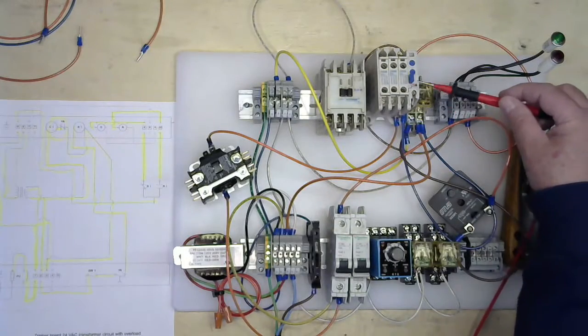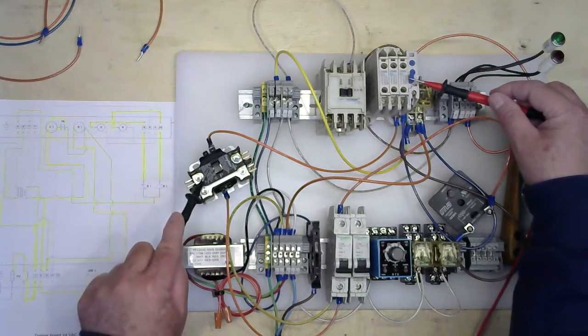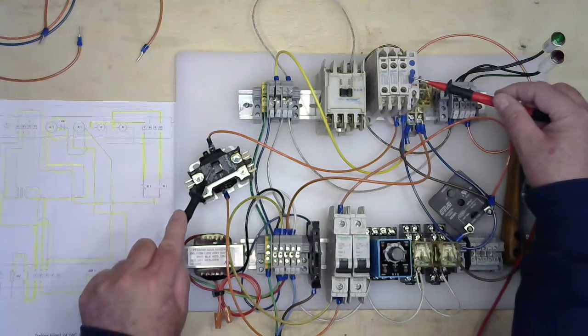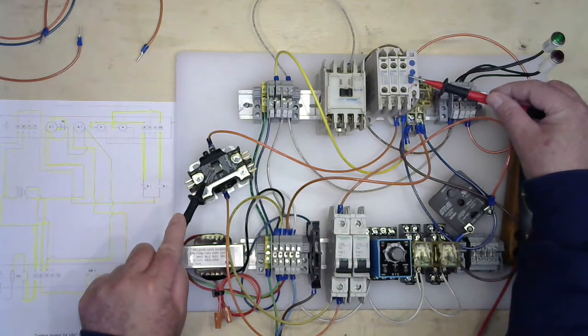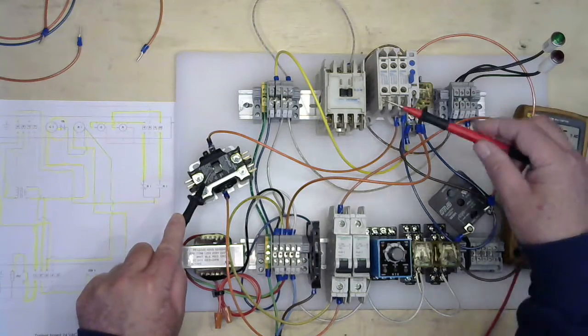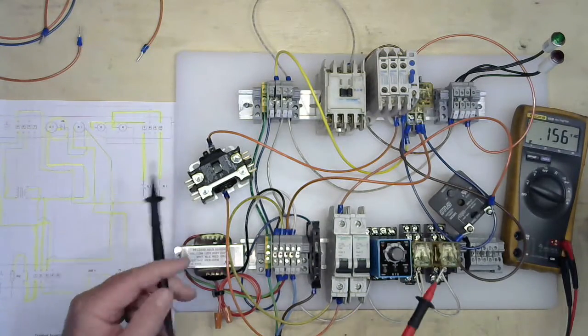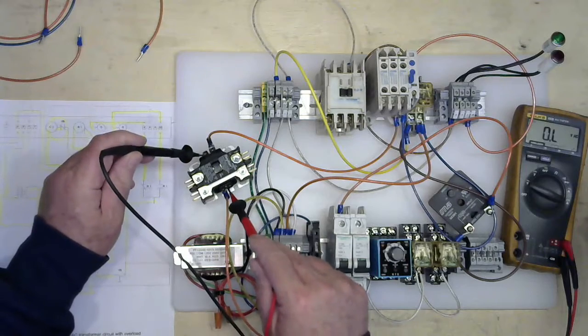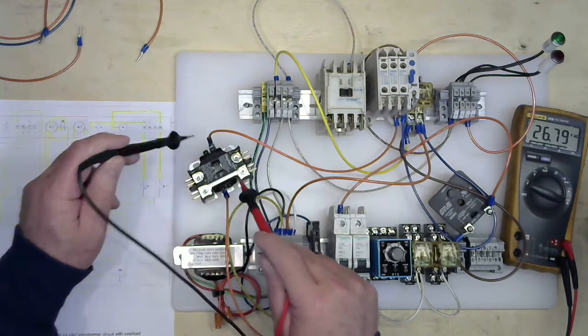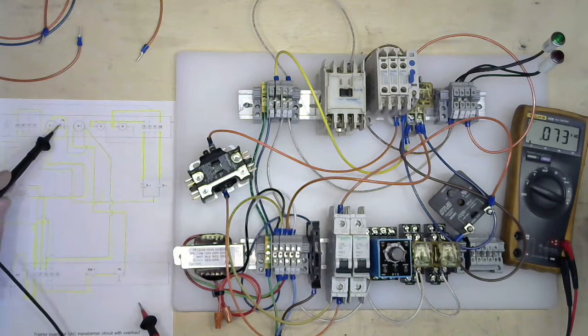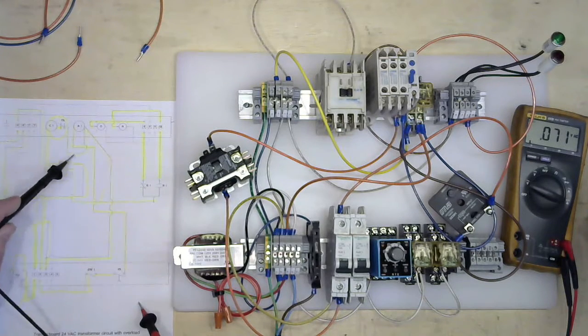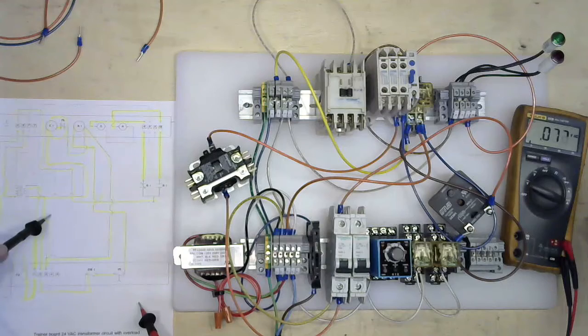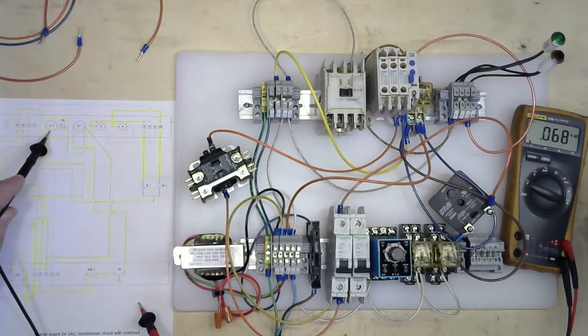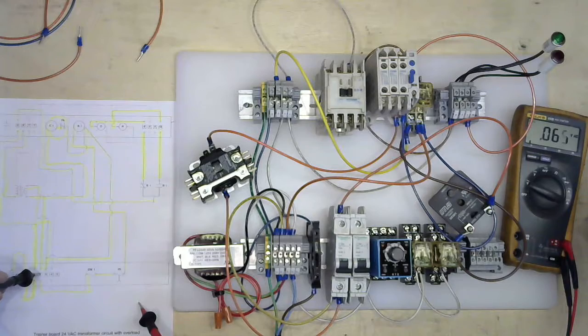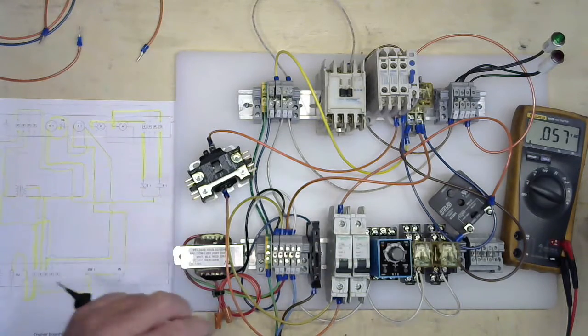I'm going to go ahead and reset the other way here. I'm going to reset, and you're going to watch this guy here. You watch it pull in once I push this down. This guy pulled in. You heard the click. And now my overload is working. So we know our overload protecting our contactor here is opening. We know that the coil of our C1 is always hot if we have the 24-volt transformer. We tested our time delay relay.